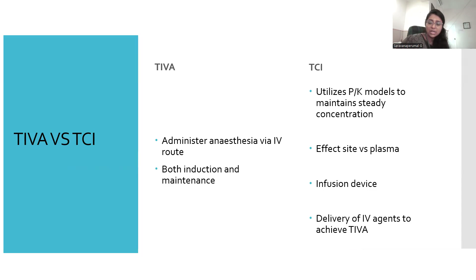The pharmacokinetic model of a TCI is a bolus, elimination and transfer model. The bolus is given to fill V1, which is the central compartment, and the infusion is given to match both V2 and V3. K10 is the elimination constant and Ke0 is the constant used for the effect site concentration. The key components of a target controlled infusion device are a user interface wherein you enter every detail of the patient, microprocessors with the pharmacokinetic software, an infusion pump which will deliver up to 1200 mL per hour, and visible and audible safety systems and alarms.